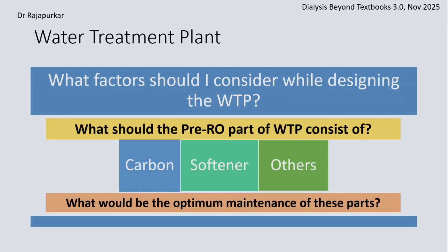particles. You may avoid using a carbon filter in my unit because that is the only source of water I get. And even at the highest time of summer, my TDS in the incoming water is 400. So I need much better mineral removal rather than chloramines. But if you don't know, then you need two carbon filters in tandem, and then you need to monitor them to see whether they are exhausted. Then you replace the unit with a new carbon filter and take the second polisher out and put a new one, and that way you keep rotating.